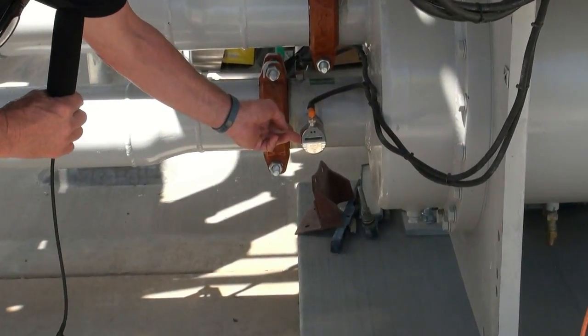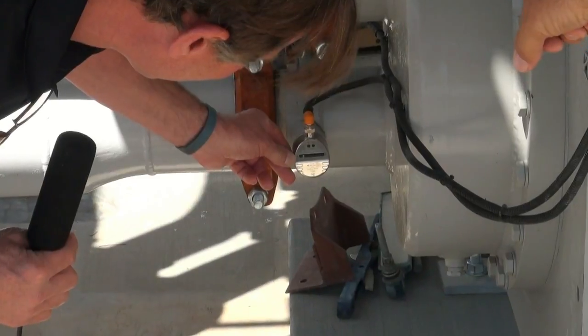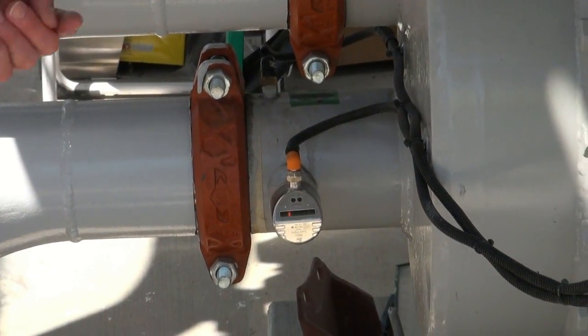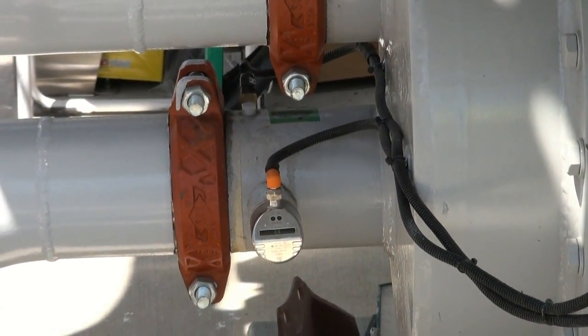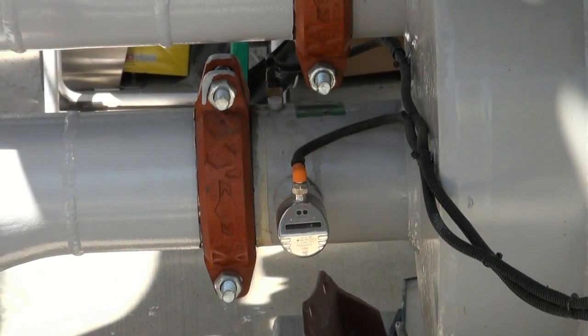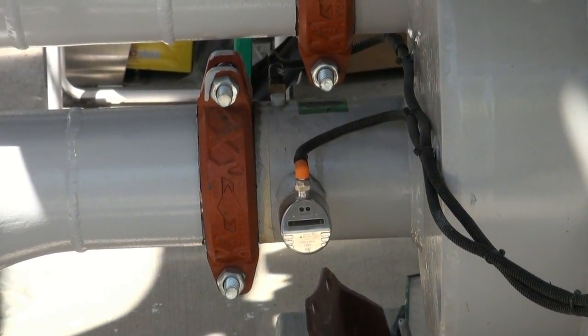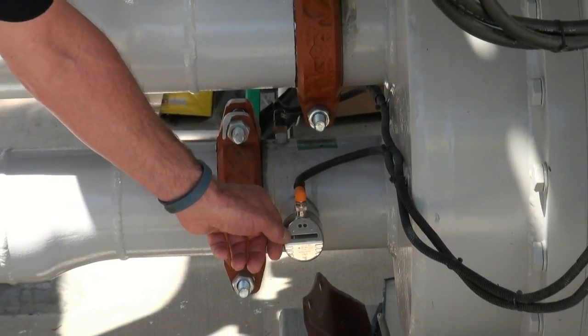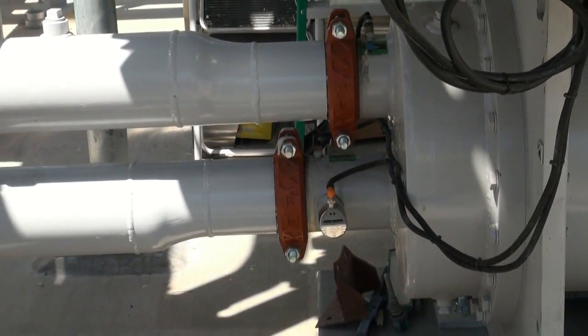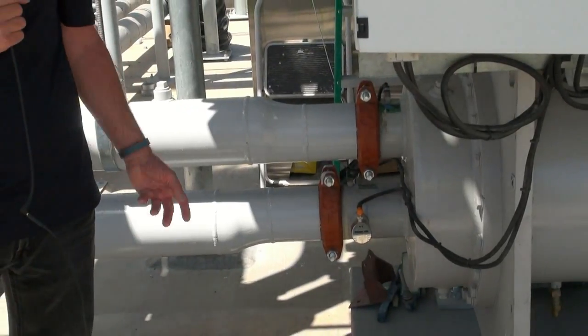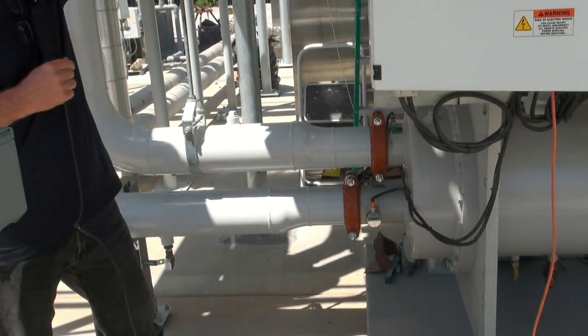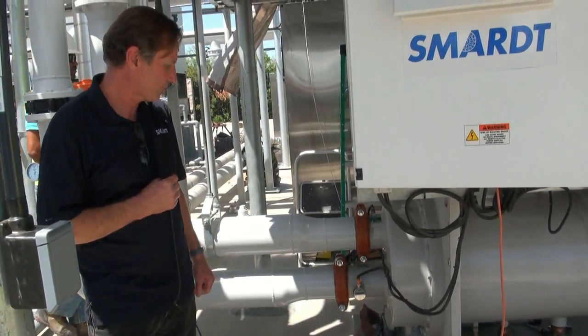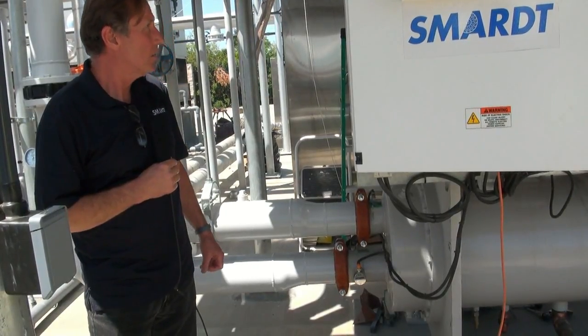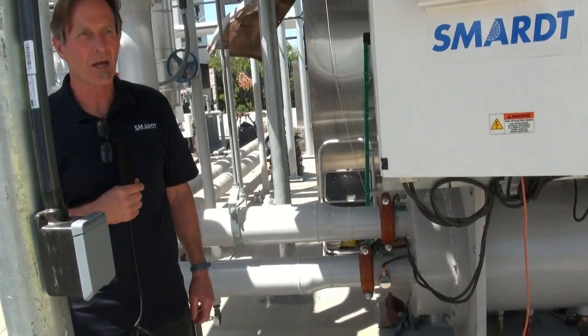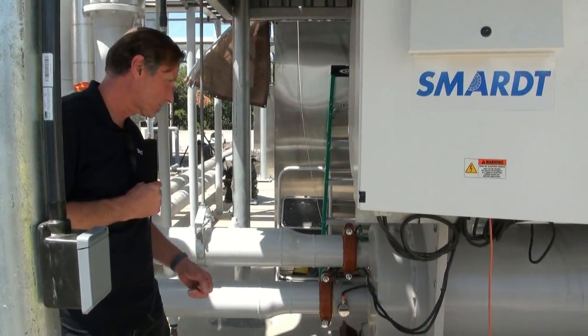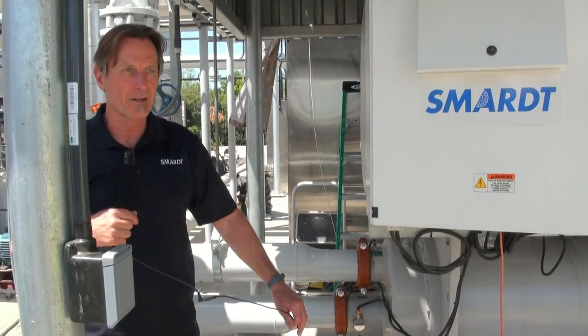There's an arrow on top there, a line on the pipe. Its flow is this direction, and that's the direction indicated. As the flow increases, your LEDs will light all the way across. Then there's an amber light, which is actually the set point. If you get below this amber light, it'll indicate a no flow situation, and that LED will go from amber to red. There's no moving parts, so it's very dependable. Same thing on the chilled water side. You've got the same type of switch there. All right, we walk around behind the chiller.